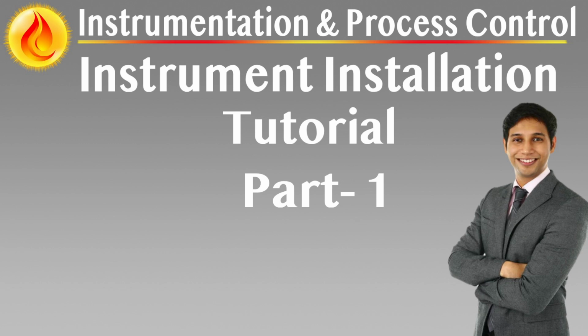Conclusion: structural discipline for safe, reliable, and maintainable measurement. Mounting remote instruments is not a secondary concern. It is a structural and reliability critical element of the entire measurement system. Every support, plate, and tubing route must reflect engineered discipline, ensuring protection against vibration, thermal cycling, and mechanical misalignment. Standardized mounting assemblies, careful routing practices, and certified connection interfaces together form the backbone of a resilient, low-maintenance remote instrument installation.